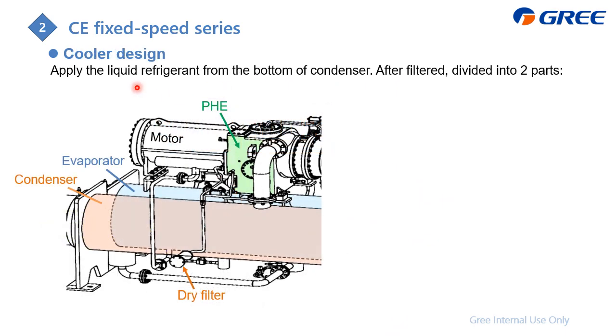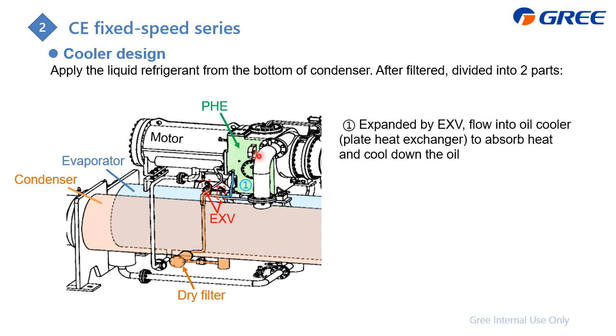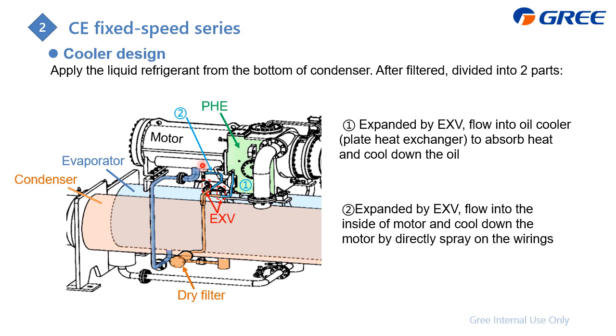And then the next is how we cool down the motor, which we also cool down with the refrigerant. In these pictures you can find the plate heat exchanger, this is the evaporator, and this is the condenser. We get the refrigerant from the bottom of the condenser, and then it comes here and divides into two passes. And also here there are the EXV. First, analyze this part. It gets expanded and then goes in to cool down the oil in the plate heat exchanger. Do you remember that? For the other pass, it goes into the motor. We spread the refrigerant directly on the motor windings to cool them down, and then the refrigerant itself becomes gas and flows back to the evaporator.